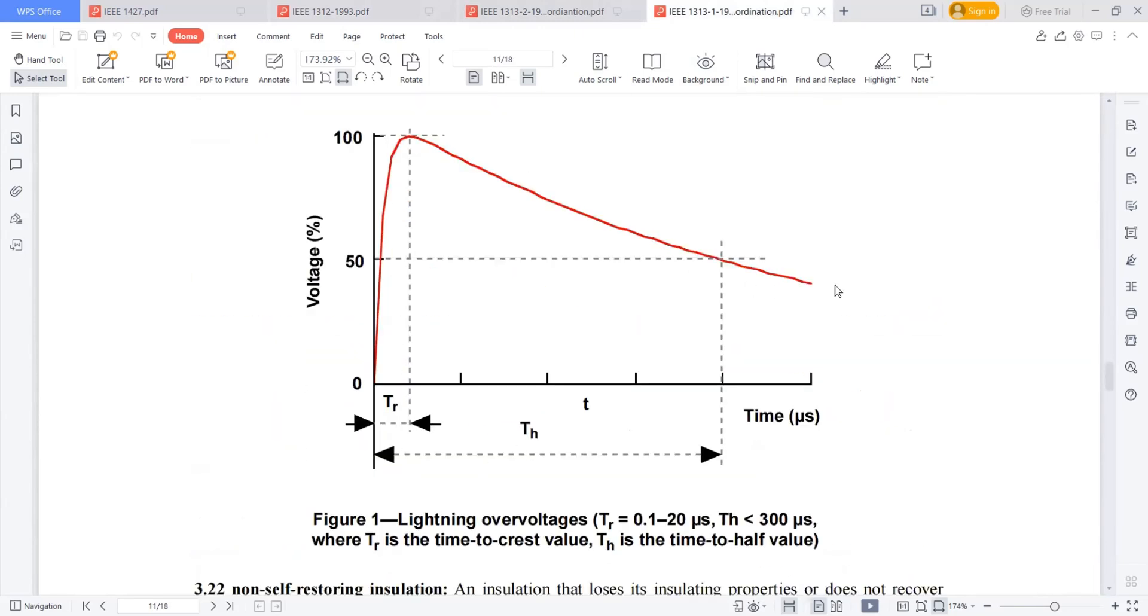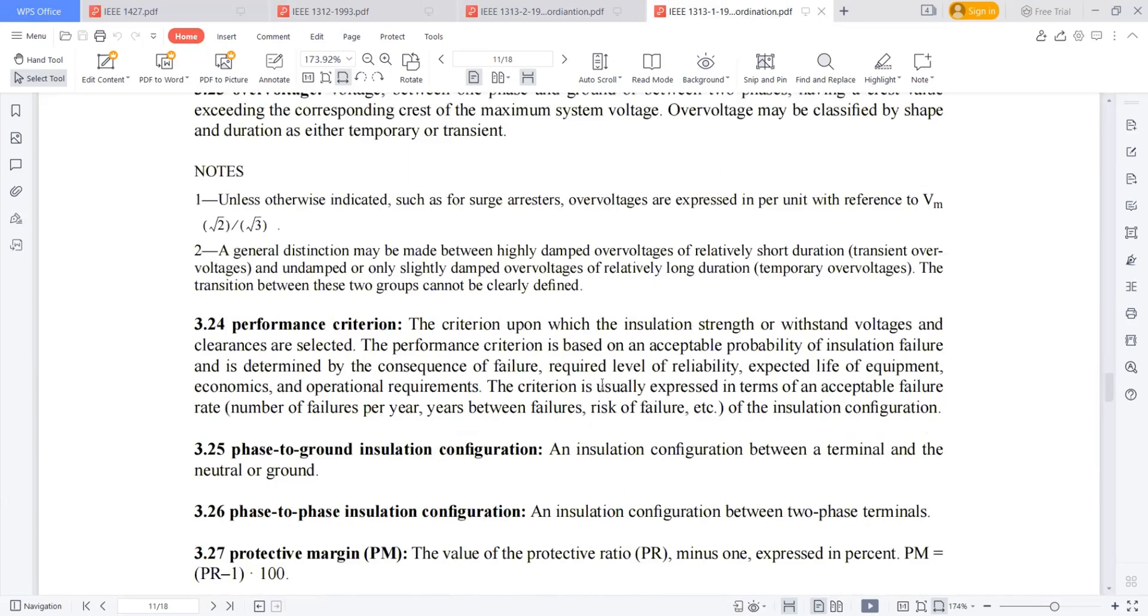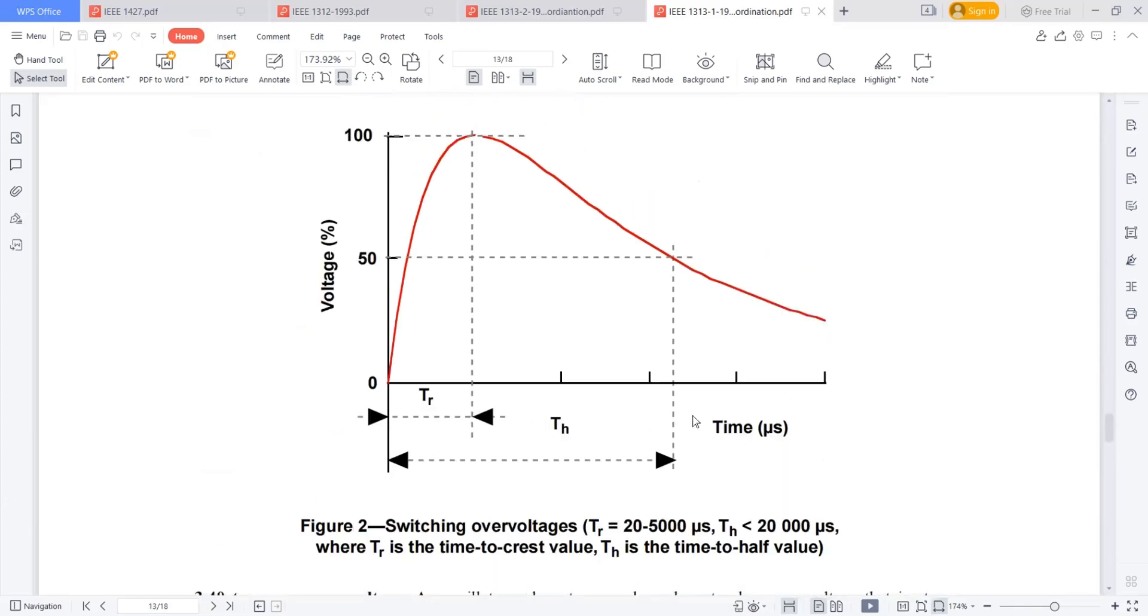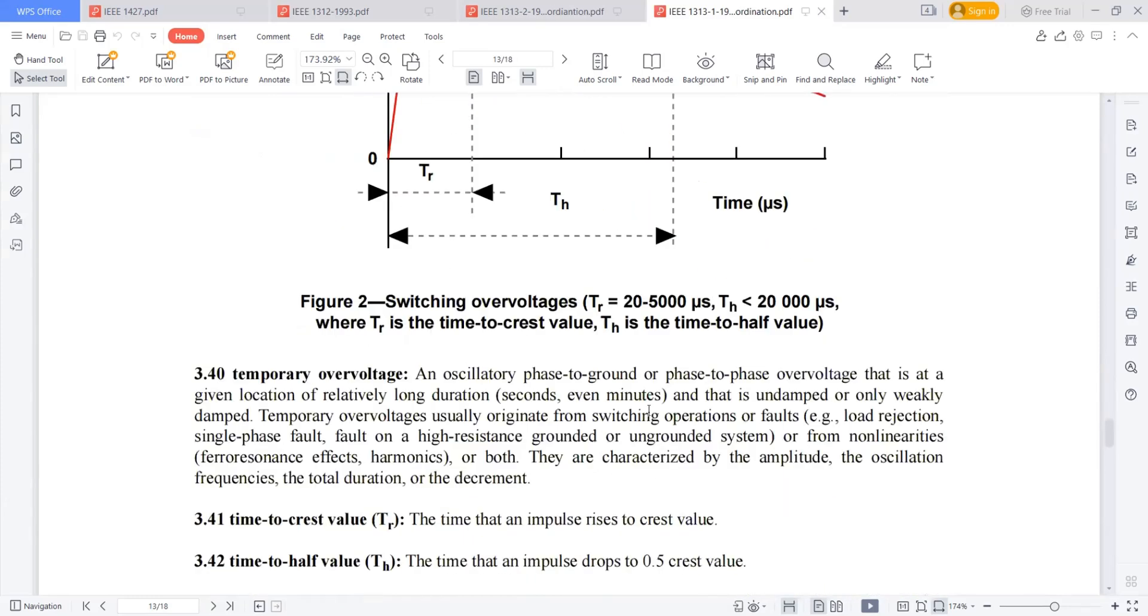So here you can see this curve. The rise time, if it is 0.1 to 20 microseconds and the tail time is less than 300 microseconds, we are calling it as lightning overvoltages. And the same characteristic with 20 to 5,000 and less than 20,000, then I am calling it as switching overvoltages.